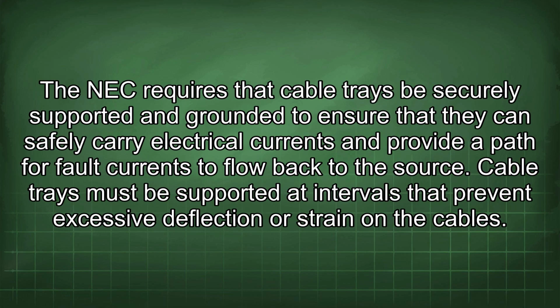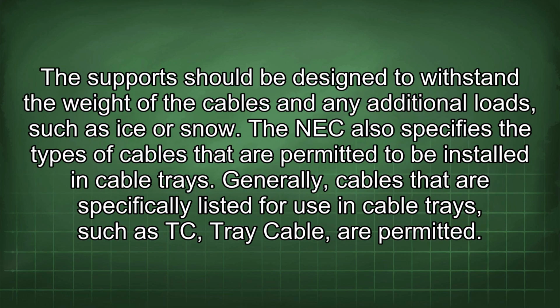The NEC requires that cable trays be securely supported and grounded to ensure that they can safely carry electrical currents and provide a path for fault currents to flow back to the source. Cable trays must be supported at intervals that prevent excessive deflection or strain on the cables. The support should be designed to withstand the weight of the cables and any additional loads, such as ice or snow.